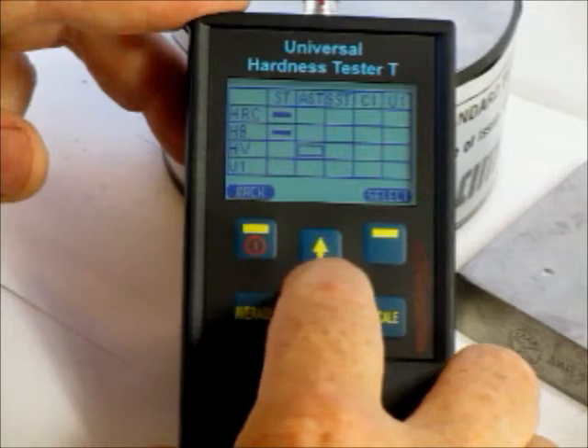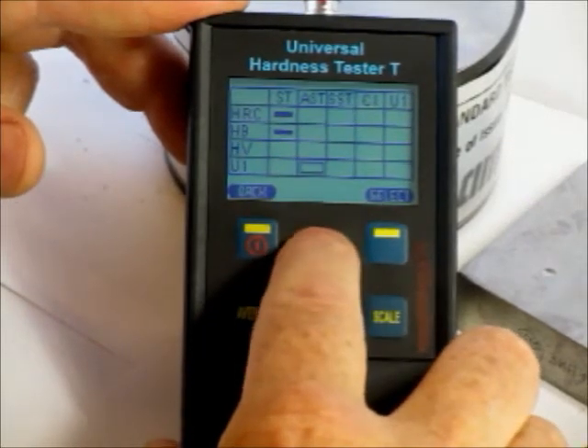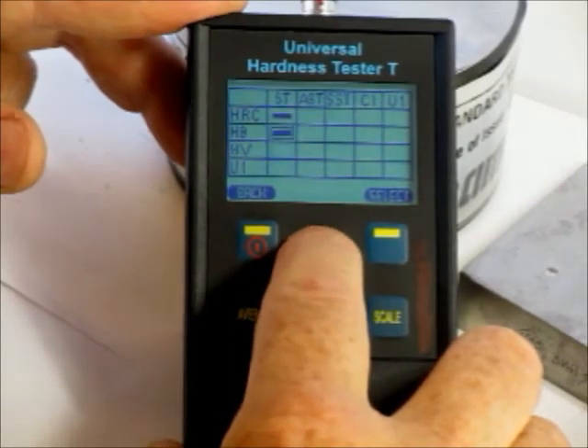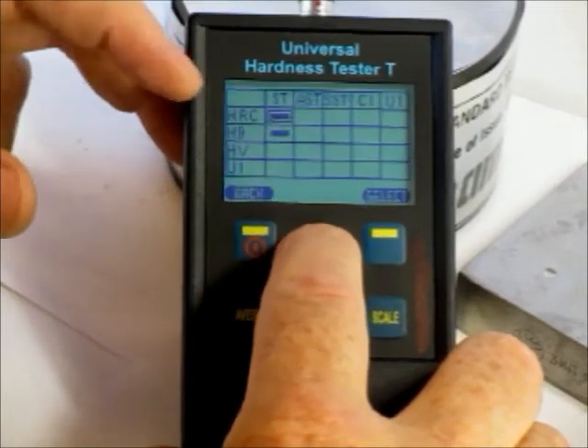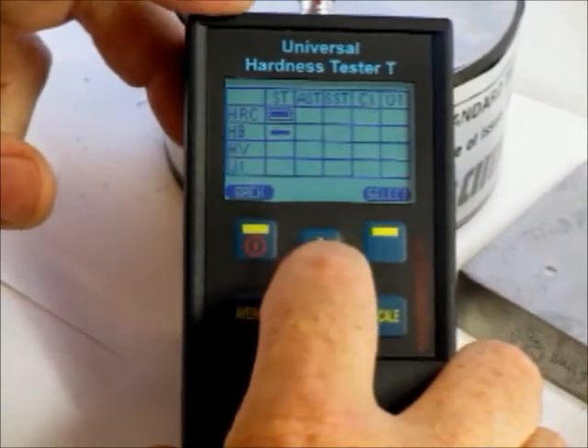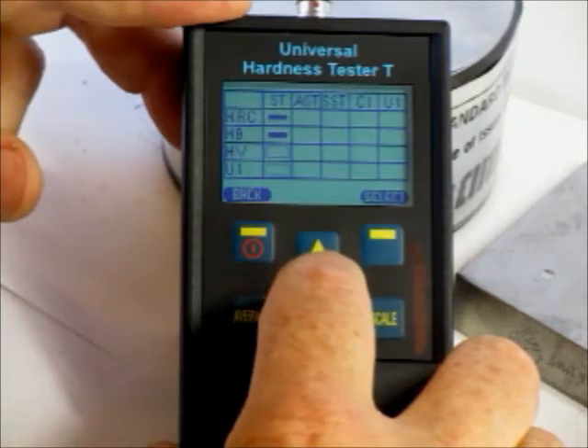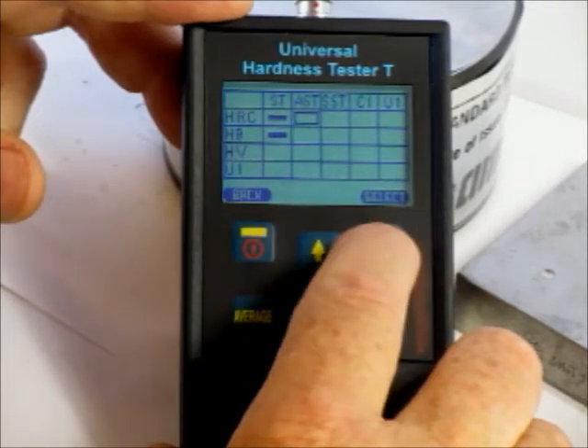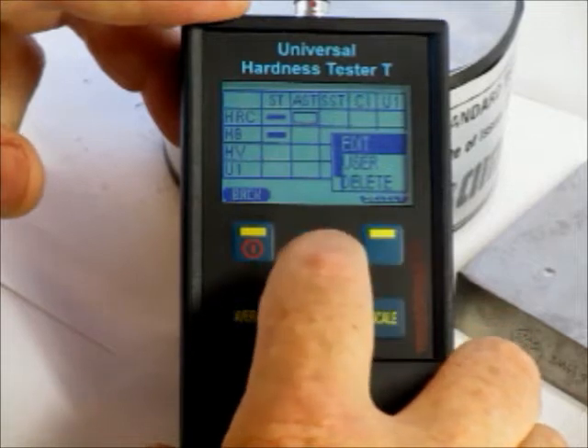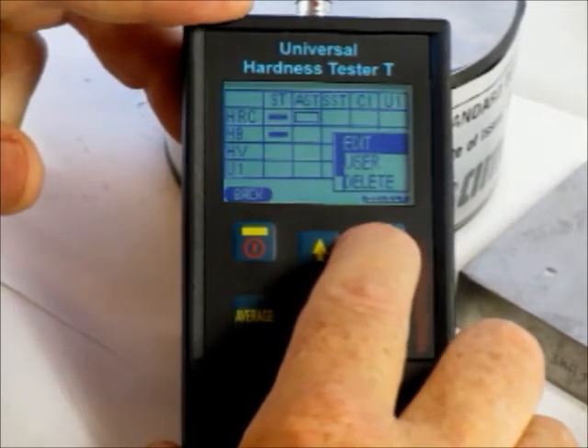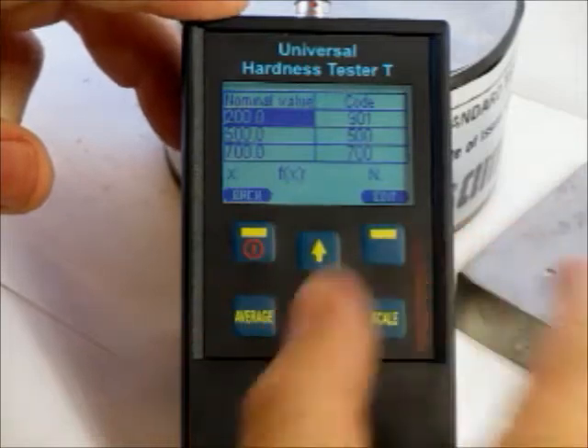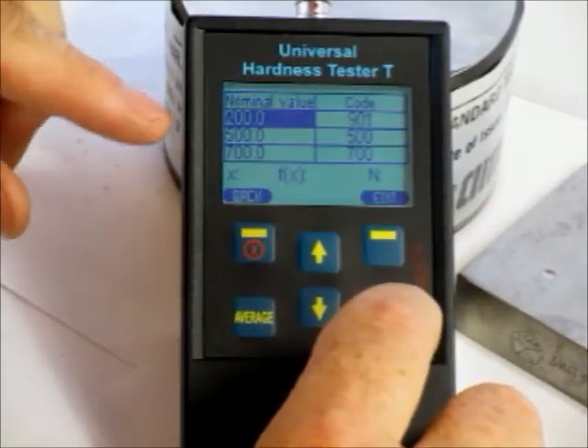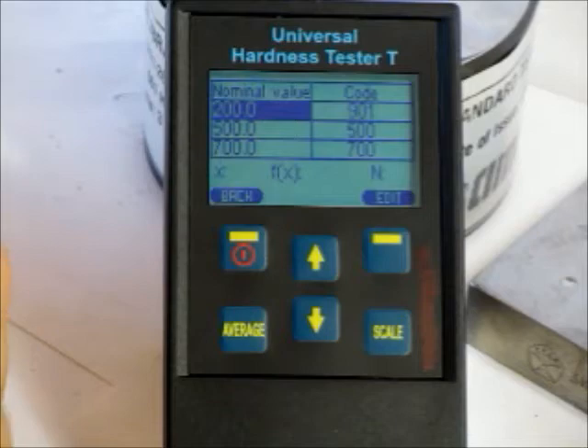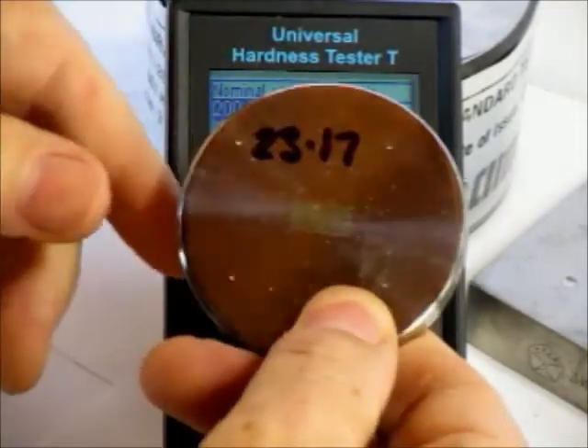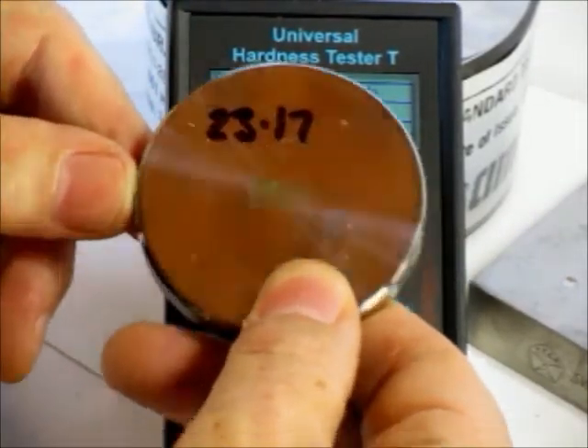So you can see I can move my cursor around, and this will be choosing to create a calibration, in this case here, for steel and Rockwell C. I don't want to overwrite the current calibrations, I want to create a new one, so I go over that field and I hit select. I want to do edit, so I hit the same button again. And now what I need to do, you can see the nominal value is showing 200. I need to change the value to whatever the test block is. And you can see the test block here is 23.17. So I need to come into this, hit edit.